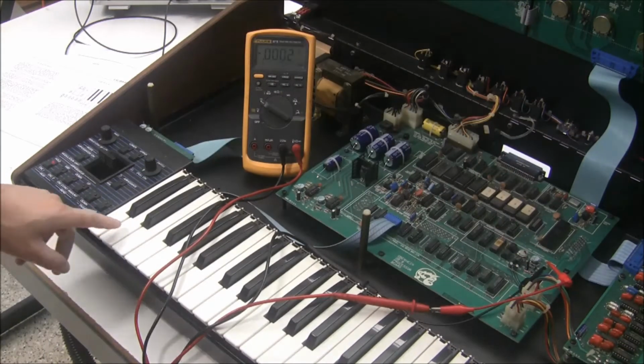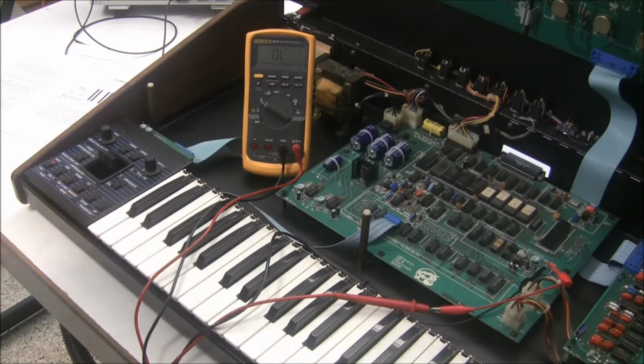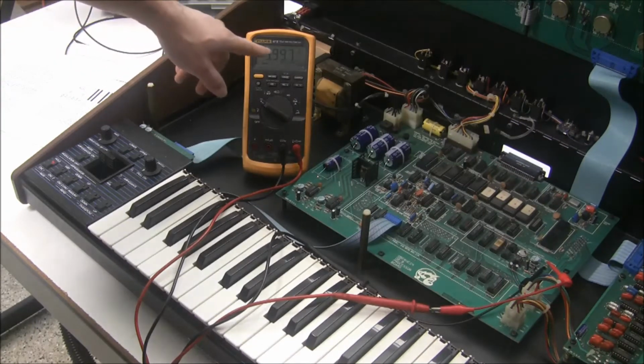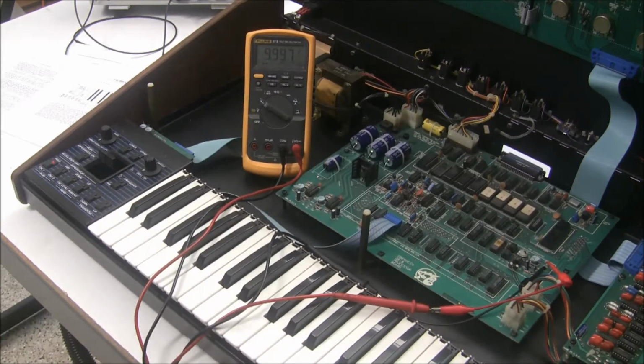So we're going to hit the next key up, which is the D, and it's going to send the highest possible number into the DAC, so all ones, and it should spit out a 10 volt voltage. And this is 9.997 volts, again, as good as we can get it with the single turn trimmers that are in there. So the DAC is calibrated well on this already, so we don't need to make any adjustments here.